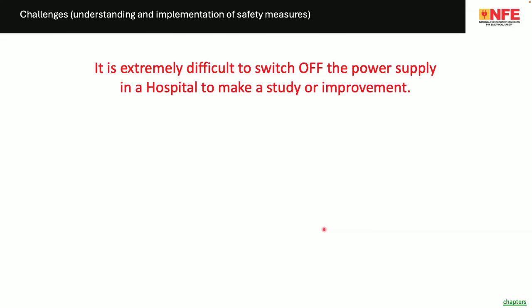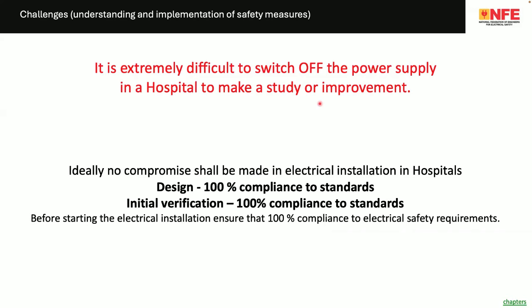And this has been included in the standards, rules, and regulations since 125 years. Even now, we don't do insulation resistance test because in a hospital, once you start electricity, forget about switching it off. You cannot really stop it. You need continuous supply in most of the cases. As a result, we violate. So the only chance for making an electrically safe hospital is whenever you design an electrical installation, you ensure that it is 100% in compliance to standard. Don't compromise. It is expensive, of course.